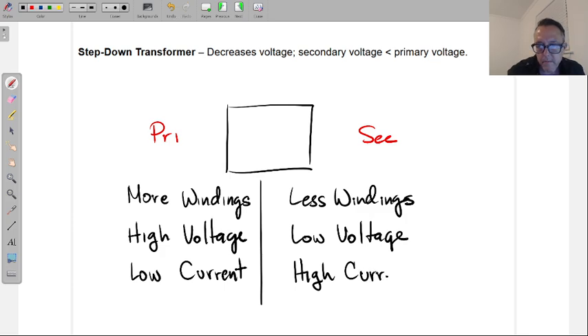So it's the opposite. It doesn't matter what the voltage is now, but you have to understand that as well. Since I have low amperage, this is going to have a smaller breaker on the primary side. This is something you see a lot in power distribution transformers, one of the transformers we run into a lot in the field. You'll notice they have a smaller breaker on the primary side and a bigger breaker on the secondary side.